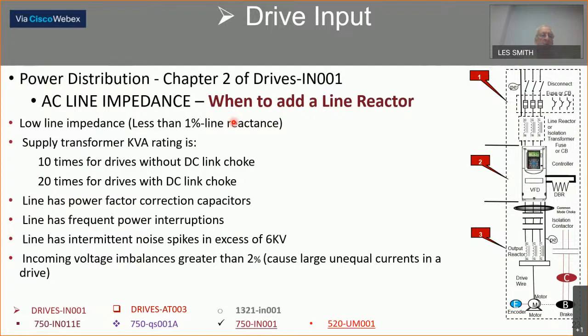Speaking of reactors, when do we add a reactor? I've handed this out to many people. Low impedance, less than 1%, highly recommended to put in a line reactor. Supply, the kVA is over 10 or 20, depending on what we just spoke about. Put a line reactor in. Power factor capacitors, it depends if they're switched or floating.